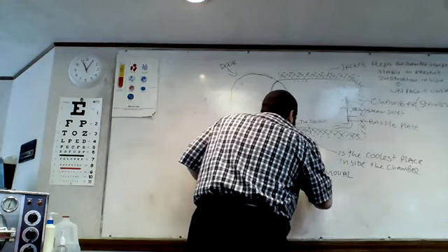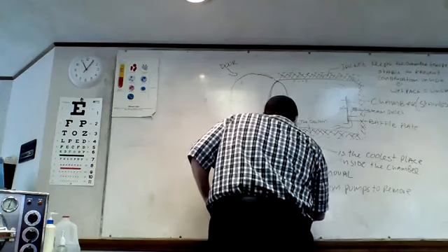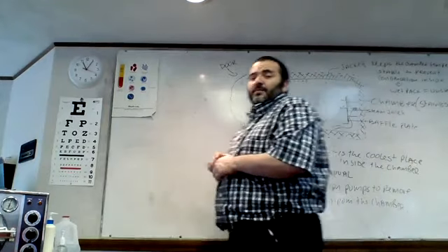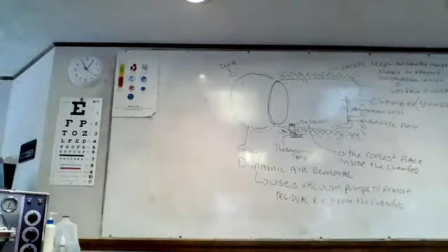So dynamic air removal uses vacuum pumps to remove residual air from the chamber. Go ahead, write that down. And I want you to understand this. Vacuum? Yeah, so we create a vacuum inside the chamber and we pump out the air from the chamber before we put the steam inside.